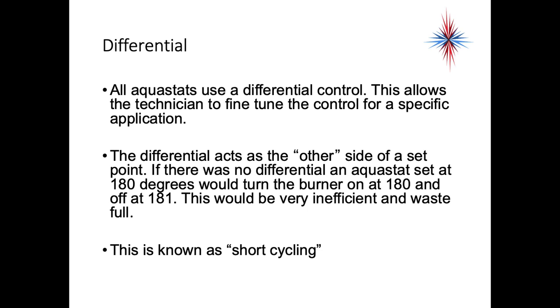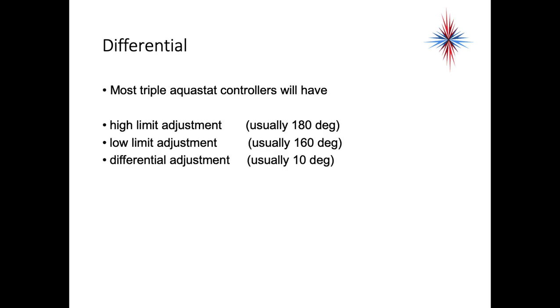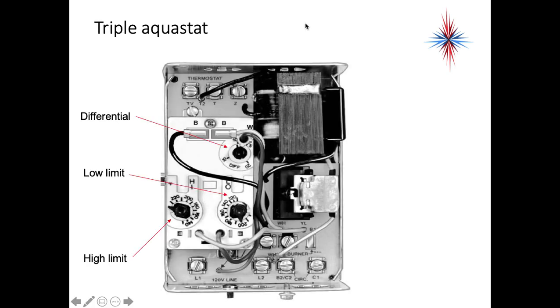All aquastats use a differential control, which allows the technician to fine-tune the control for a specific application. The differential acts as the other side of a setpoint. If there were no differential, an aquastat set at 180 degrees would turn the burner on at 180 and off at 181 — very inefficient and wasteful of fuel, known as short cycling. Most triple aquastat controllers have a high limit adjustment at 180 degrees, a low limit adjustment at 160 degrees, and a differential adjustment, usually 10 degrees.